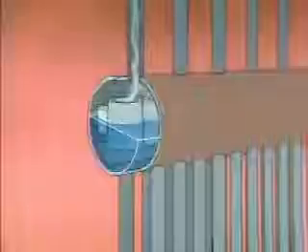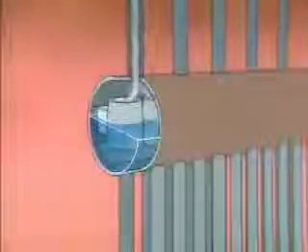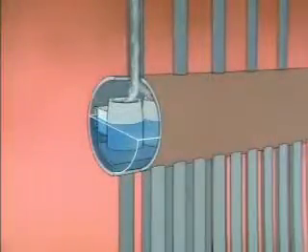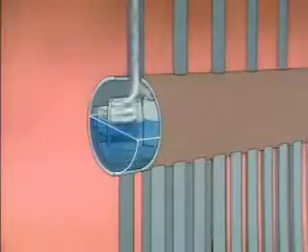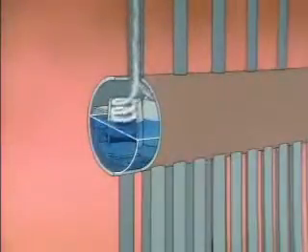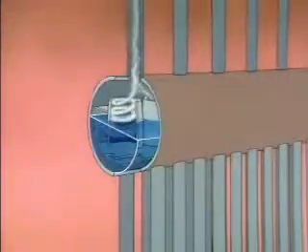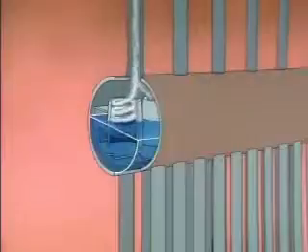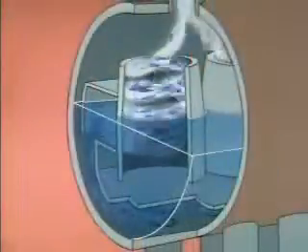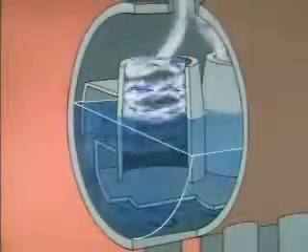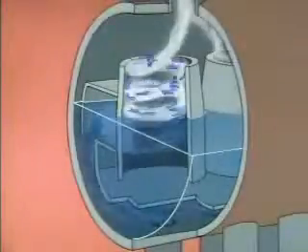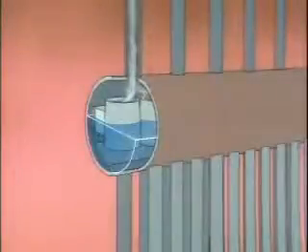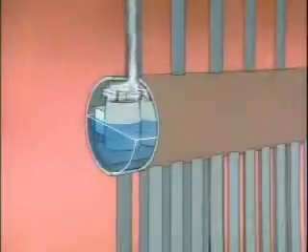One type of moisture separator is a centrifugal or cyclone separator located in the steam drum. It works by directing the steam-water mixture into a circular chamber; the circular shape causes the mixture to swirl around, creating centrifugal force. This force flings moisture droplets against the chamber walls, where they run back into the drum, while the lighter steam flows out the top. Some boilers use a dryer along with centrifugal separators.